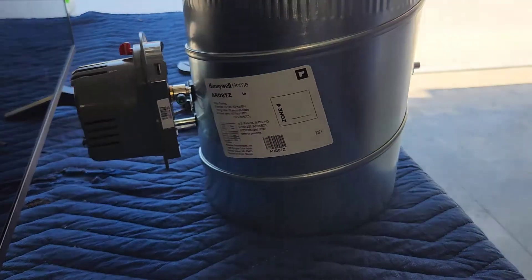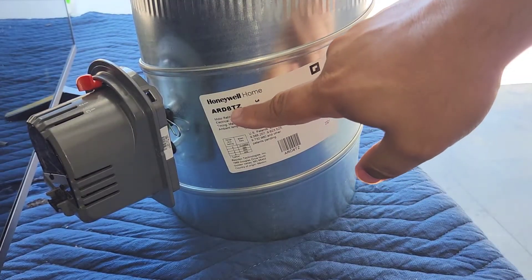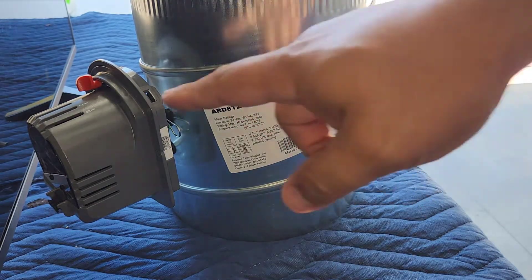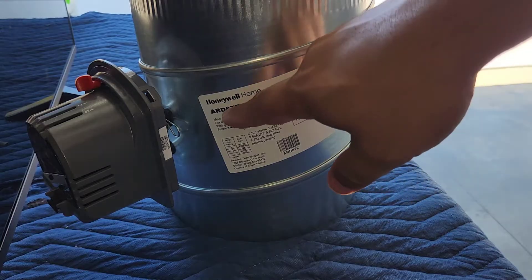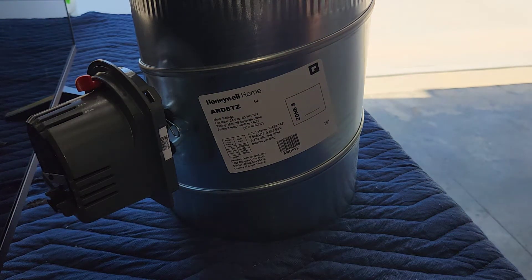Now when you're using this as a zone damper, typically you want it to be normally open and then it would power to close. That way, for some reason, your zone module went bad, maybe the actuator went bad, that this would default to an open state instead of closing, closing off airflow and potentially doing damage to your unit.